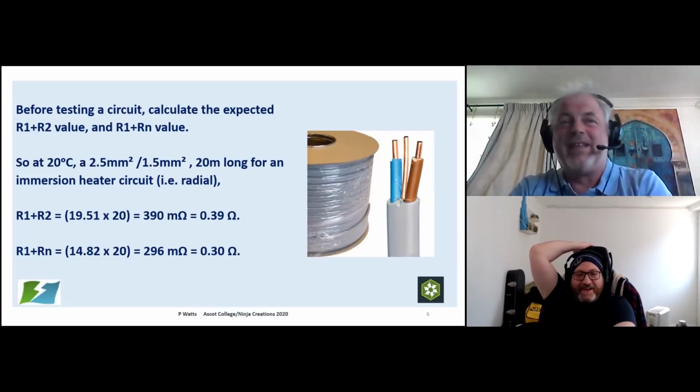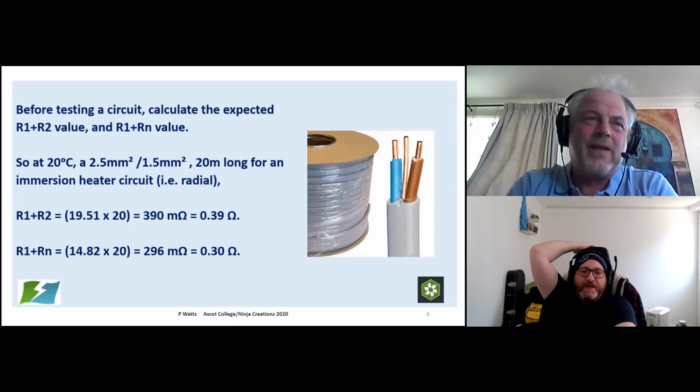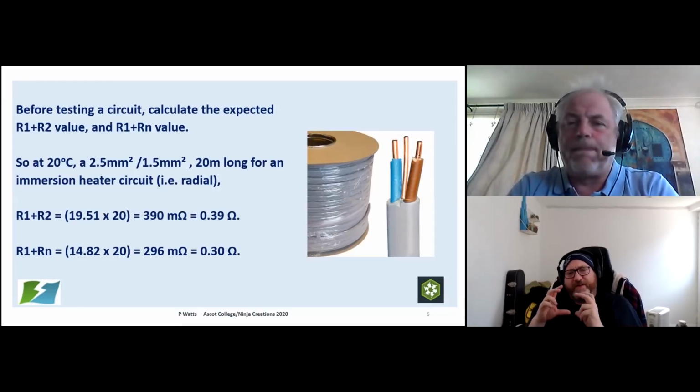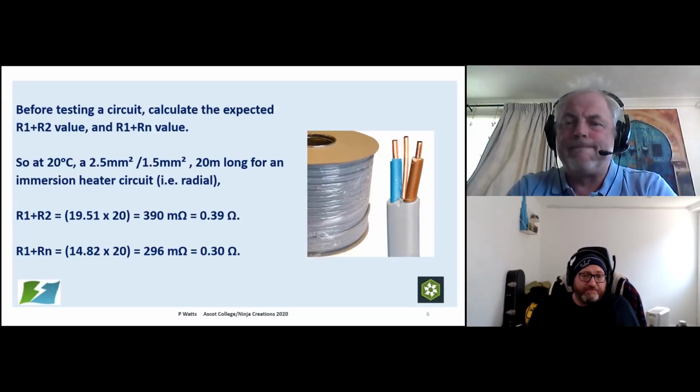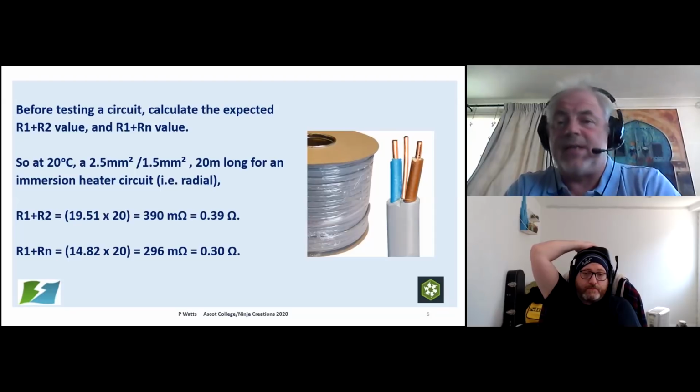Yeah, beer and rugby. Mark says, what is our view on the NICEIC CalCard calibration for a daily check of an MFT? So the CalCard, you're probably familiar with that. It's like a credit card size thing with some inline resistors. It's like a little resistance checker. Anything that will check that resistance, as long as it's accurate, as long as it hasn't got damaged.